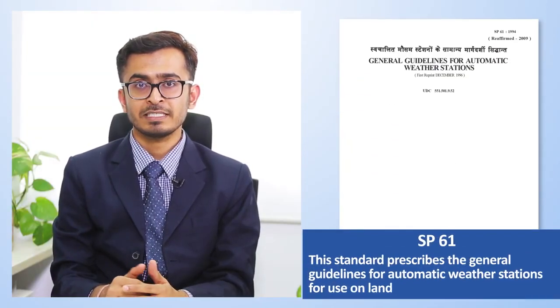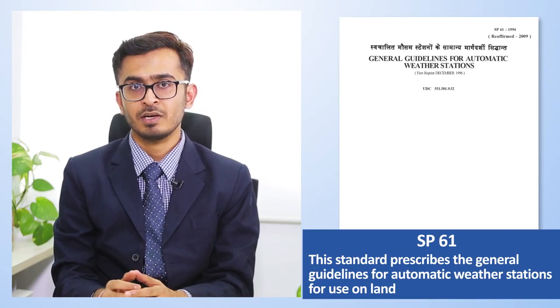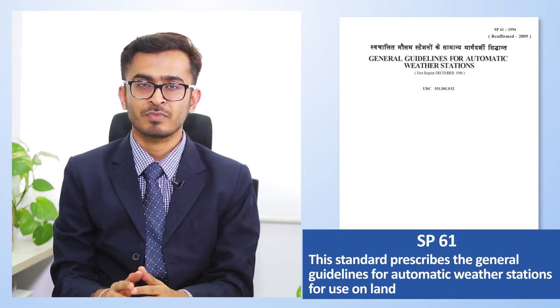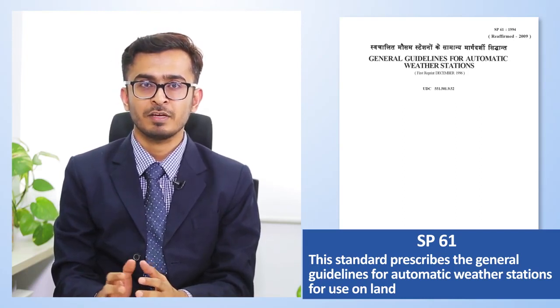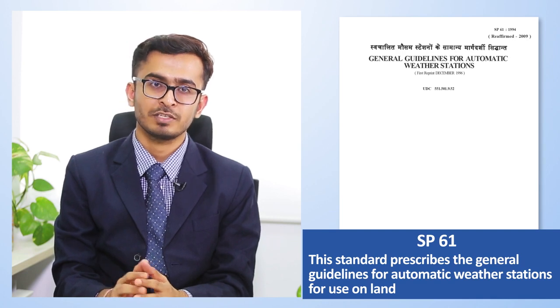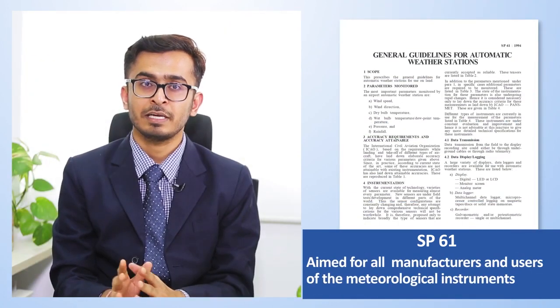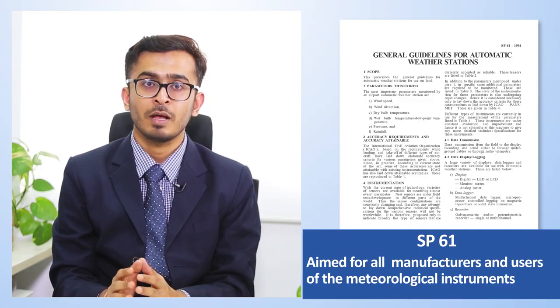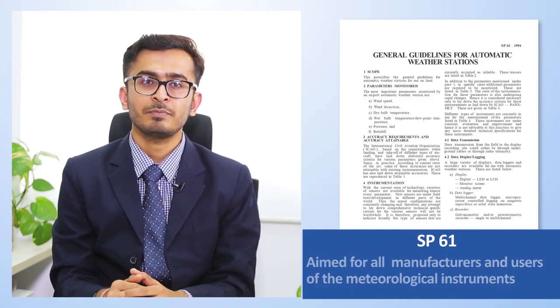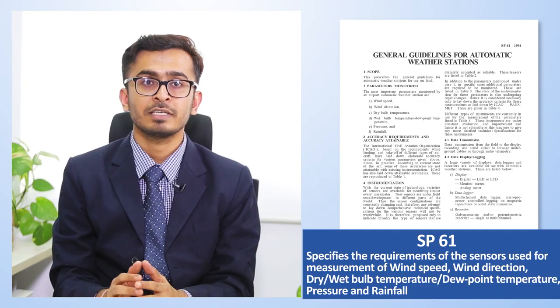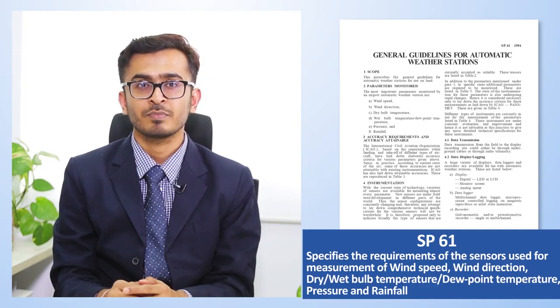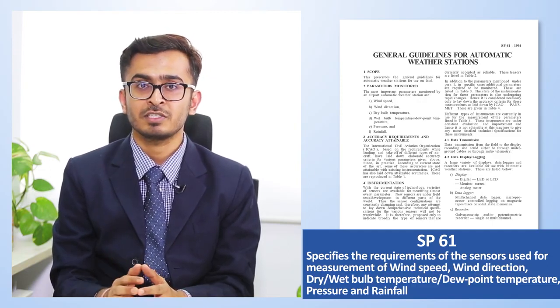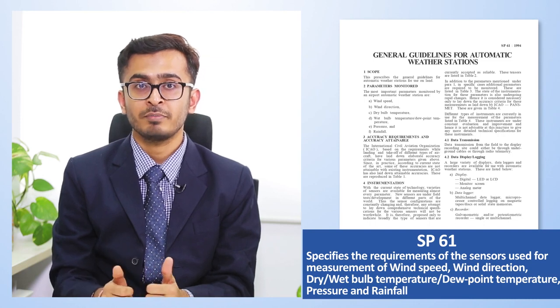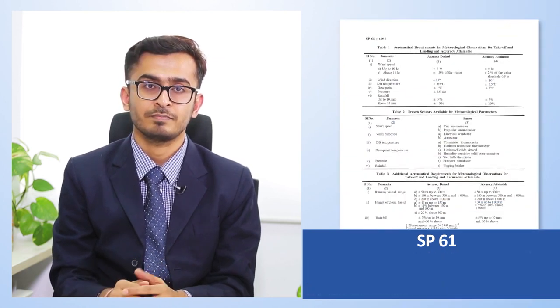The standard SP 61, which is formulated by BIS for automatic weather stations, helps in predicting nature's behavior from empirical evidence or observation. This standard SP 61 is aimed at all the manufacturers and users of meteorological instruments. This standard prescribes the minimal requirements for sensors used for measuring the wind speed, wind direction, dry bulb temperature, wet bulb temperature, dew point temperature, pressure and rainfall, etc.